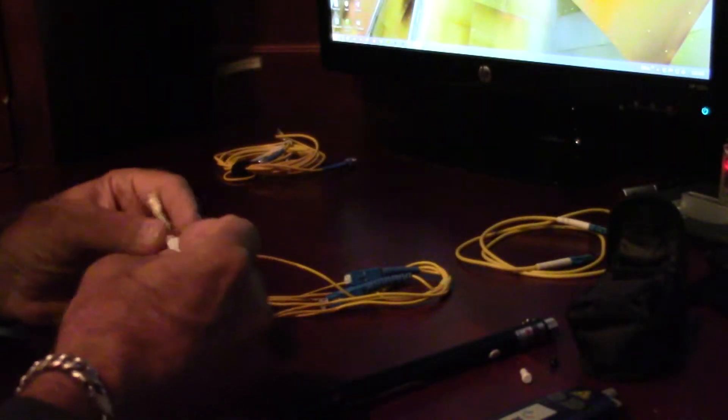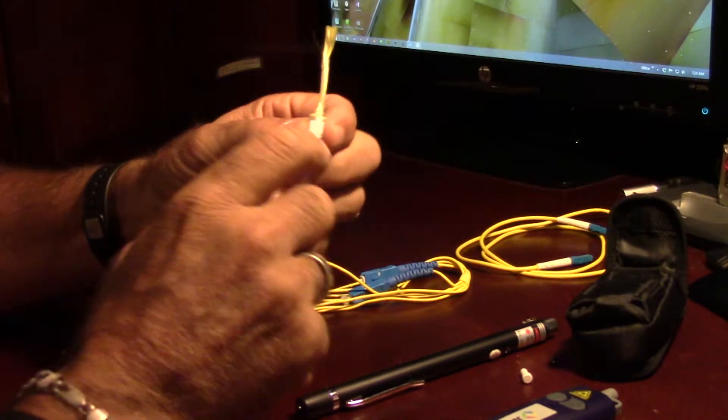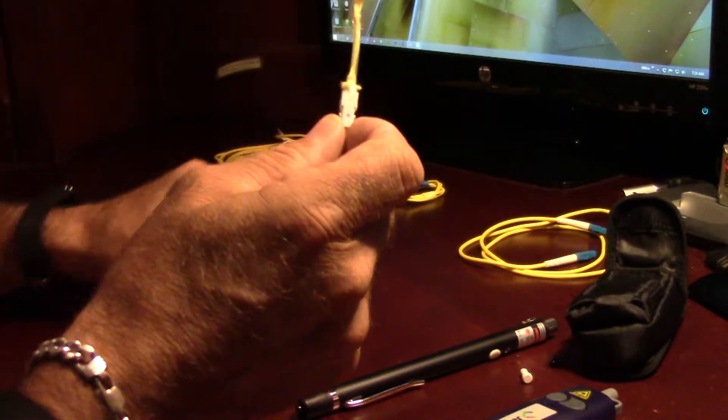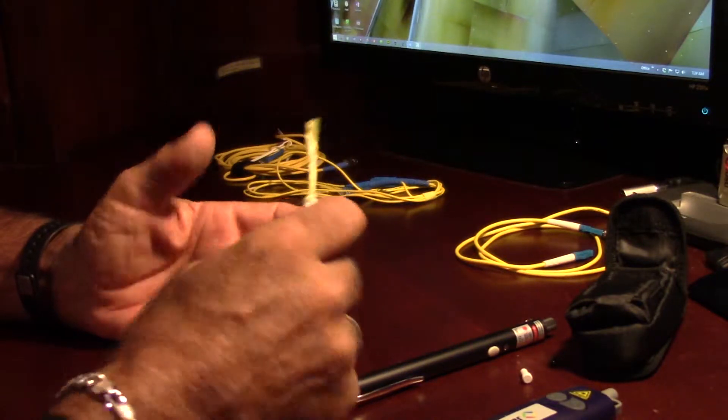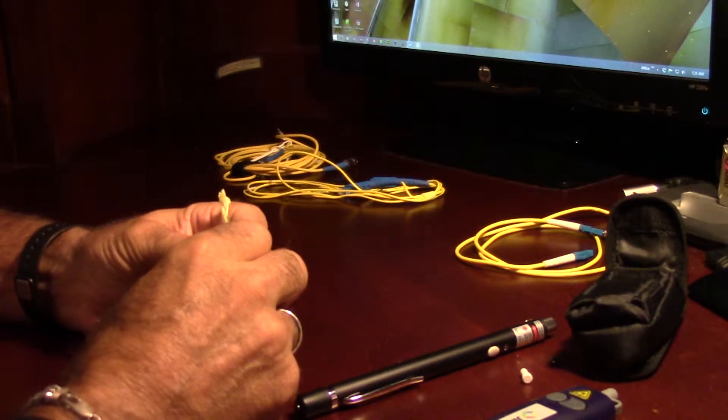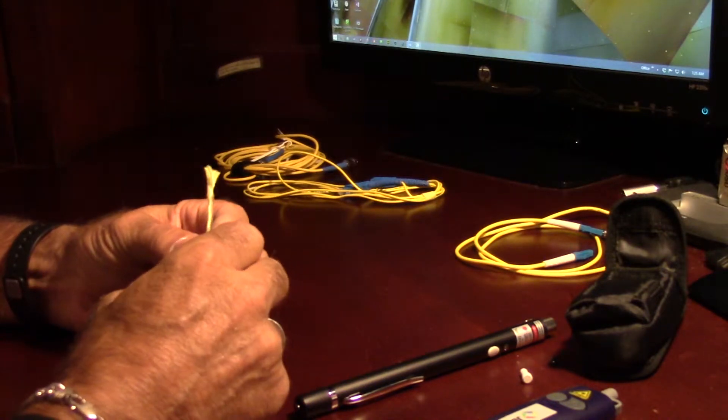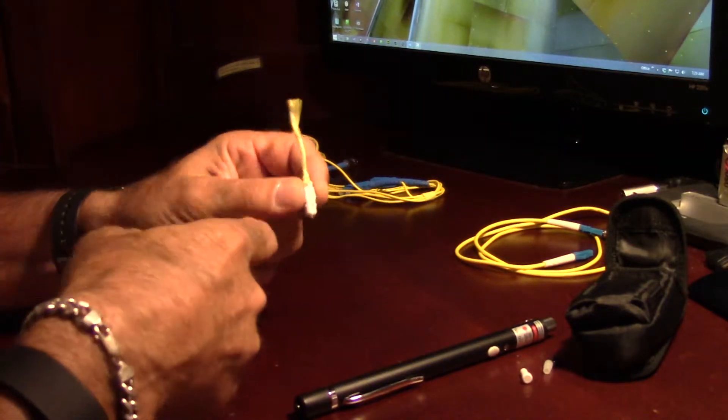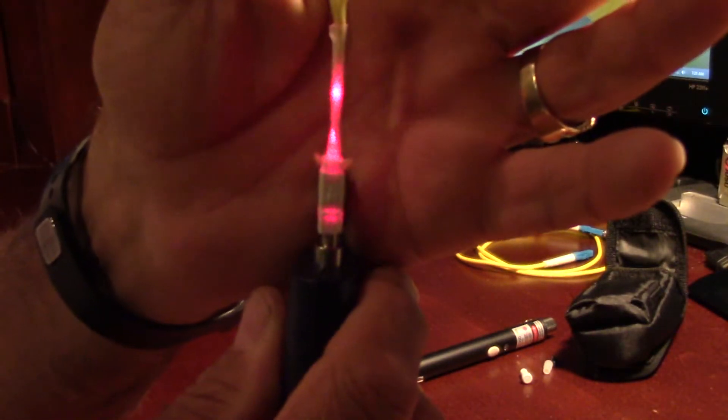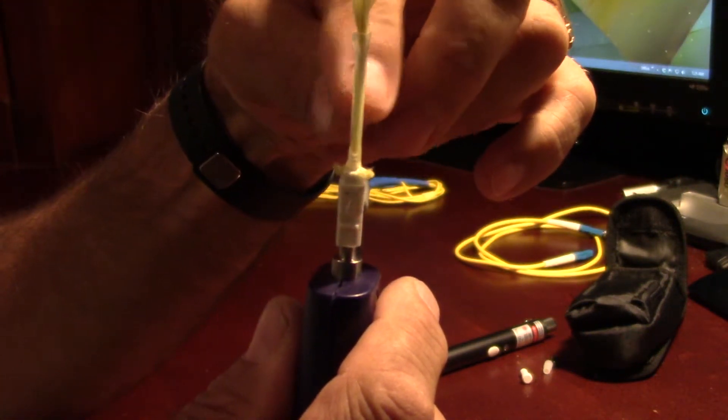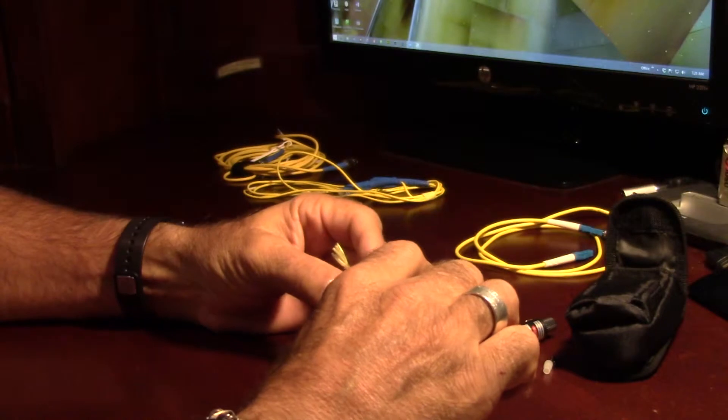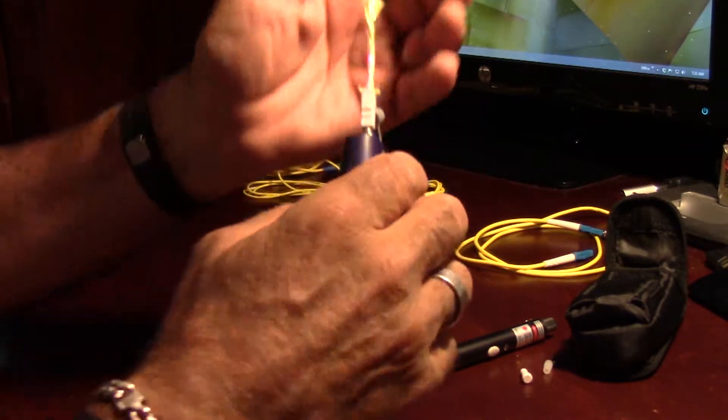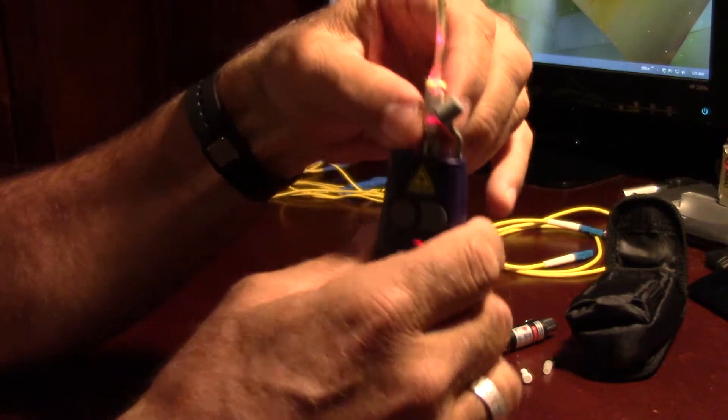All right, we're back. This was a connector on the end of one of my launch bags. I was doing a fiber training class the other day and my launch bag didn't seem like it was acting correctly. I was getting some strange readings and what I was seeing was what I wasn't expecting. So we started fiddling around and basically the quick thing was this is a splice on connector. The quick thing to do was to go ahead and turn on the visual fault locator and you'll notice that right here, this flashing light right there, is a break in the splice. So super high loss, it was just acting really crazy.